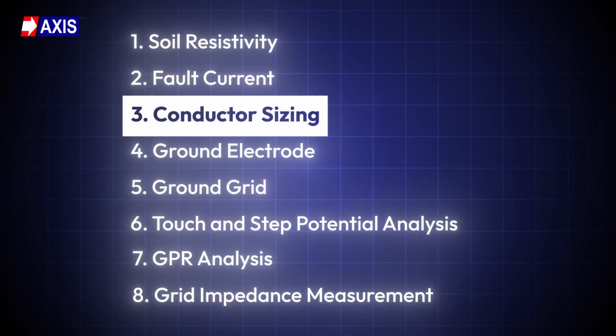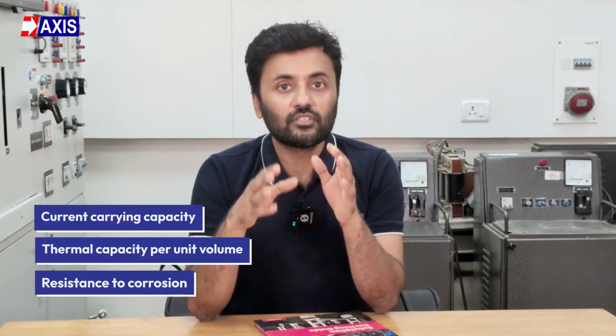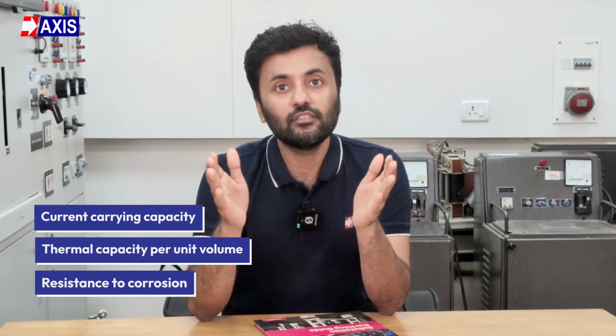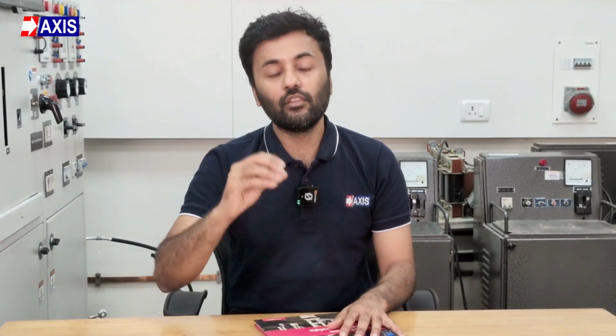Now, let's calculate conductor sizes. With the fault current known, the next step is sizing the conductors that will carry that current safely through the earthing system. The conductor needs to be selected based on 3 properties. Firstly, its current carrying capacity. Secondly, the thermal capacity per unit volume. And thirdly, its resistance to corrosion. If the conductor is undersized, it will not survive the fault current. It will heat up, degrade, and eventually fail, leaving your earthing system compromised exactly when it is needed the most.